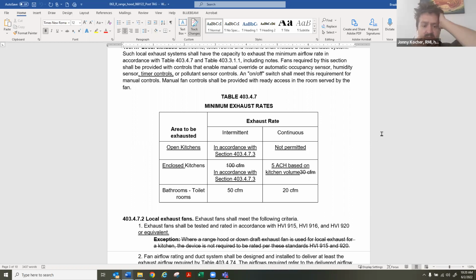And then for enclosed kitchens, if the continuous ventilation rates are chosen, then it's based off of 5 air changes based on kitchen volume, where an enclosed kitchen is defined according to the definition above from ASHRAE 62.2. And then we have intermittent for both open and closed kitchens pointing to section 403.7.2, which is below. Can you scroll down?